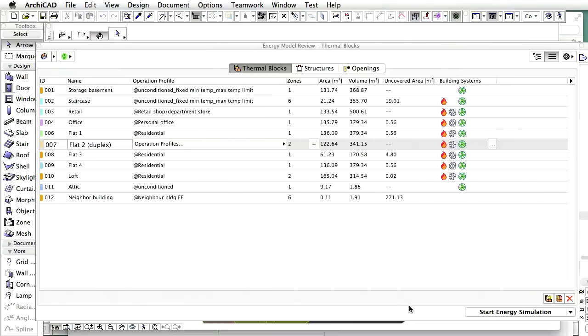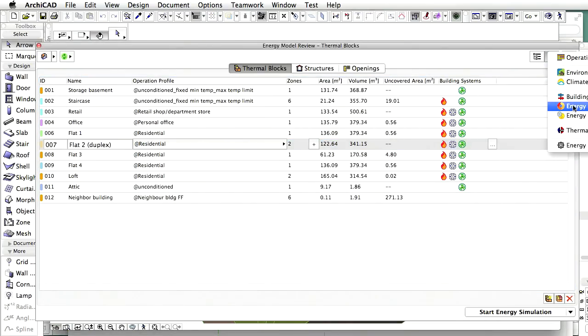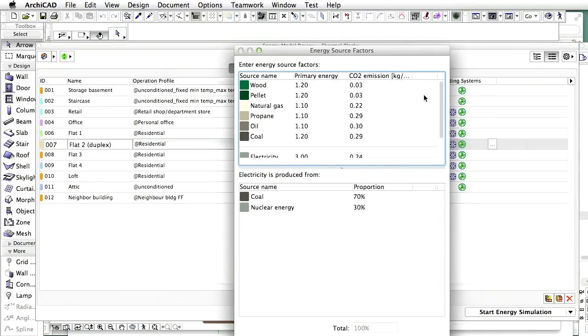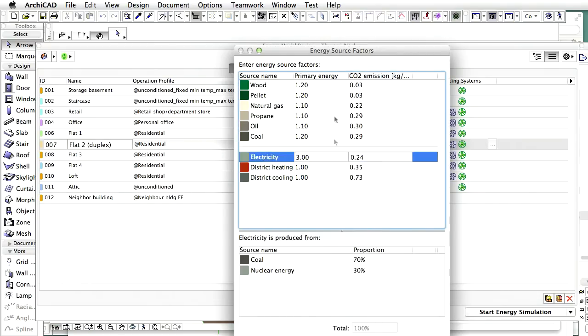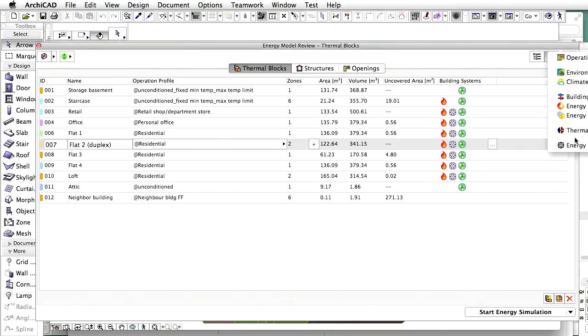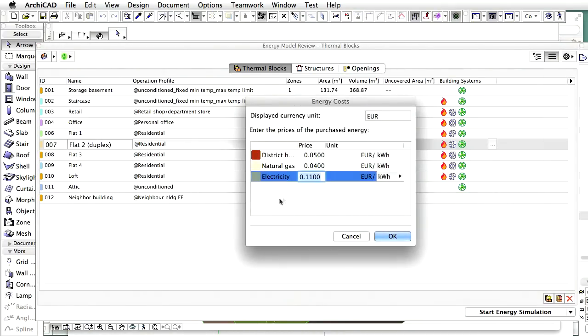Finally, let's check out the energy source factors dialog where the different primary energy and CO2 emission factors are defined. The primary energy and CO2 emission calculations are based on these values. Electrical power, for example, is produced from 70% coal and 30% nuclear facility in the region where the example project is located, which defines the carbon footprint and primary energy associated with electricity consumption. Energy sources, aka fuel types, are defined for each building system individually via the dedicated dialogs, while fuel prices and currency are specified in the energy costs dialog.